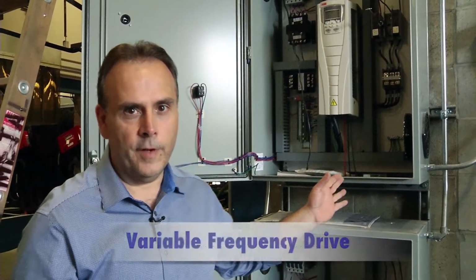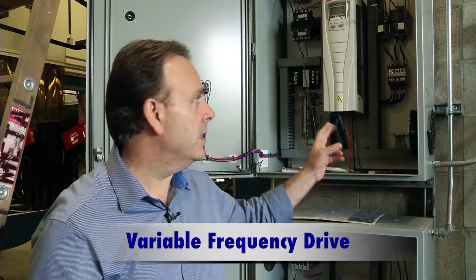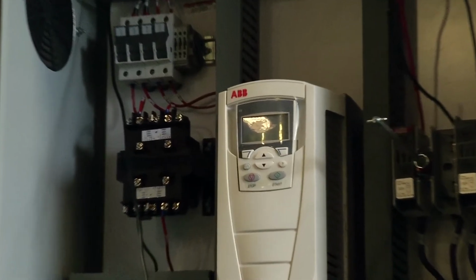Okay, we're here looking at a typical variable frequency drive. This device is what's used to vary the speed of the fan. Essentially what it does is it takes AC synchronous current at 60 Hertz, converts it to DC, and then back to AC, but at a different frequency, anywhere from 0 to 60 Hertz. So if you want to run the fan at 50% speed, you're essentially creating 30 Hertz electricity to an AC synchronous motor. So that's how we achieve variable speed on both the supply and exhaust.